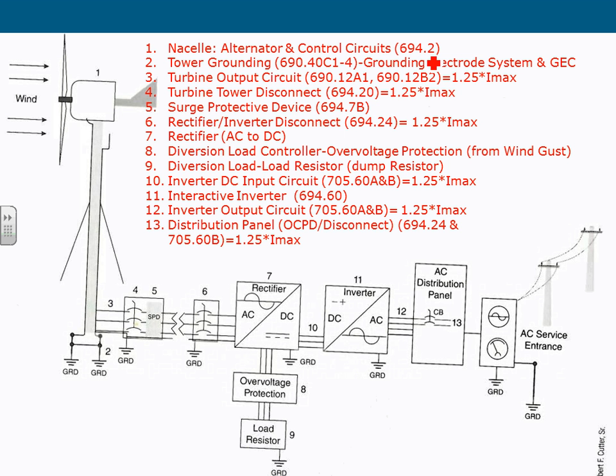You can tie it to the rebar in the foundation? Absolutely, if it qualifies, yes, absolutely. Concrete encased electrode, that's what rebar is. So if you have a foundation over here properly grounded, a concrete encased electrode in direct contact with Mother Earth, that will qualify as your, this number two is called grounding electrode system. Grounding electrode system: a ground rod or the concrete encased electrode, rebars of the foundation.